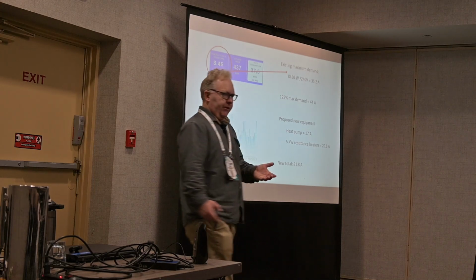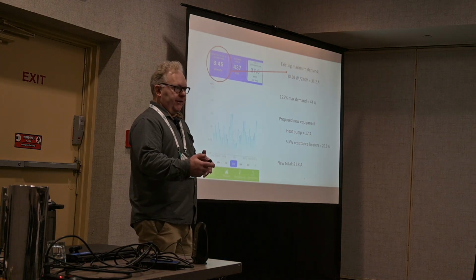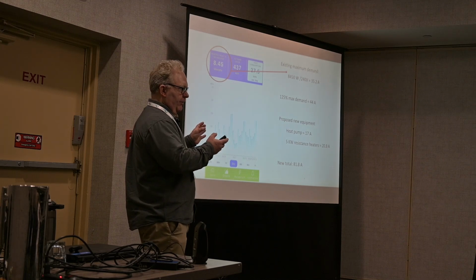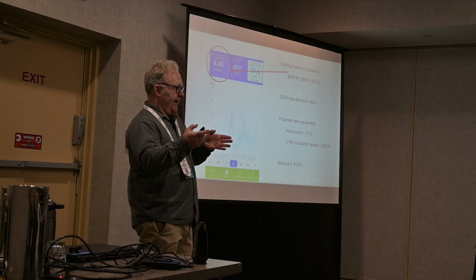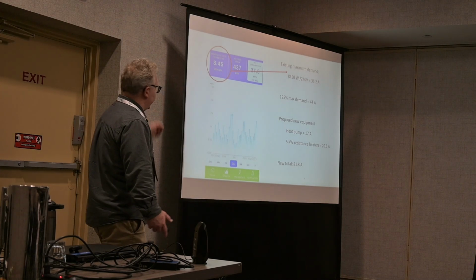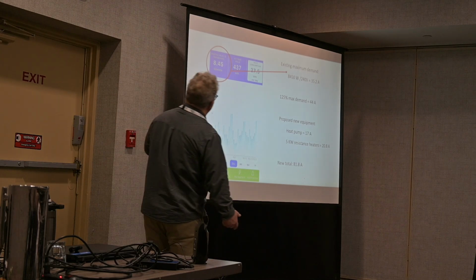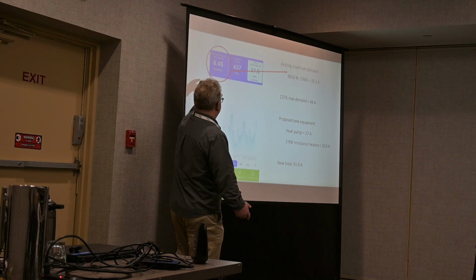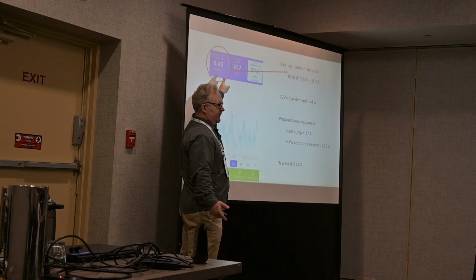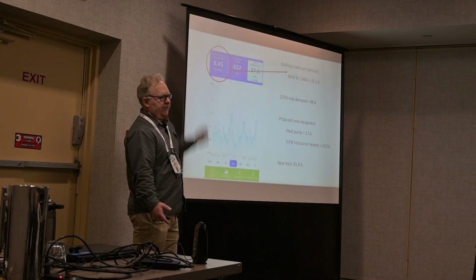So this is a screenshot from Emporia Vue. It's a home energy monitor that has little circuit transducers that you clip both into your mains for your panel, but also you can monitor individual circuits. And I'll look at some of that circuit monitoring data in the next couple slides. But on the home screen, it'll tell you what the monthly peak 15-minute demand is. So this is exactly the piece of information you need to do this calculation.